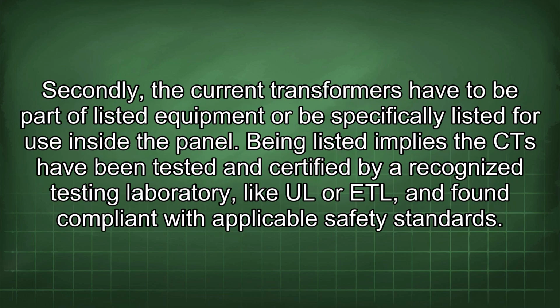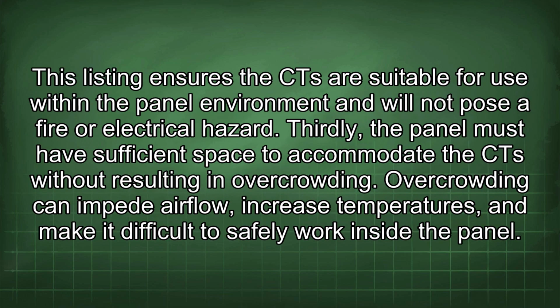Secondly, the current transformers have to be part of listed equipment or be specifically listed for use inside the panel. Being listed implies the CT have been tested and certified by a recognized testing laboratory like UL or ETL and found compliant with applicable safety standards. This listing ensures the CT are suitable for use within the panel environment and will not pose a fire or electrical hazard.